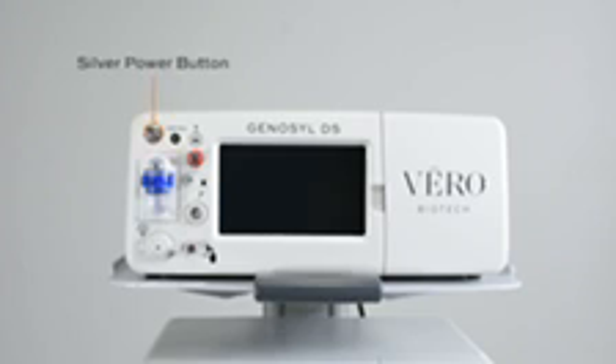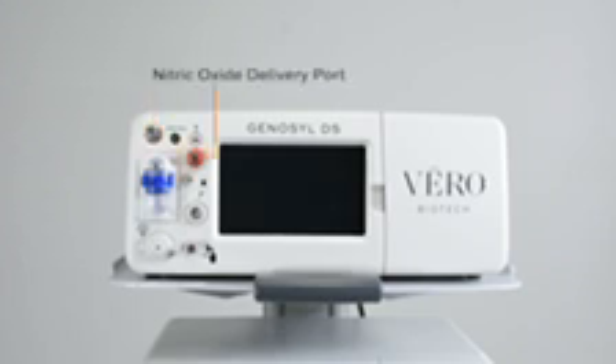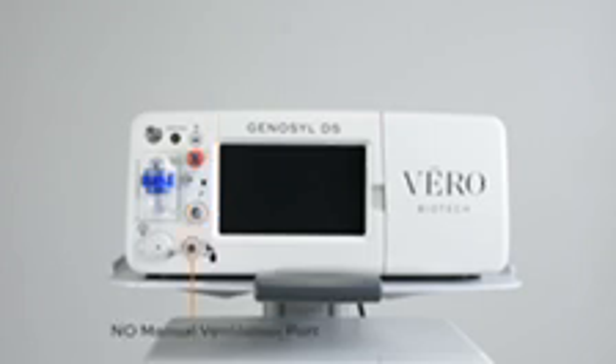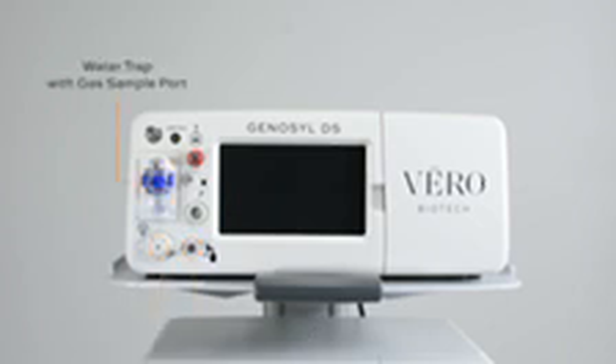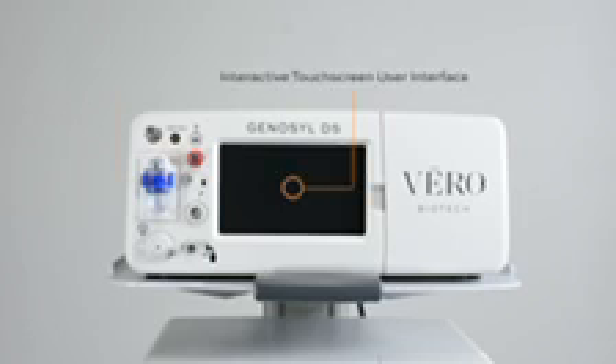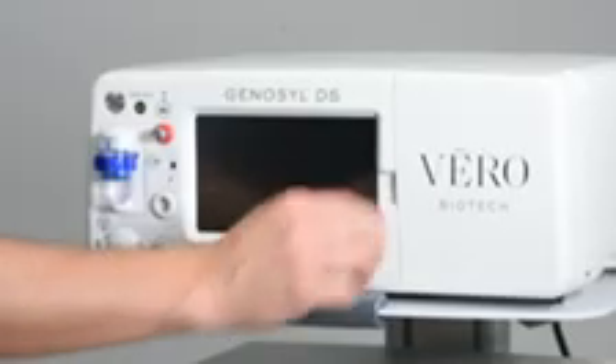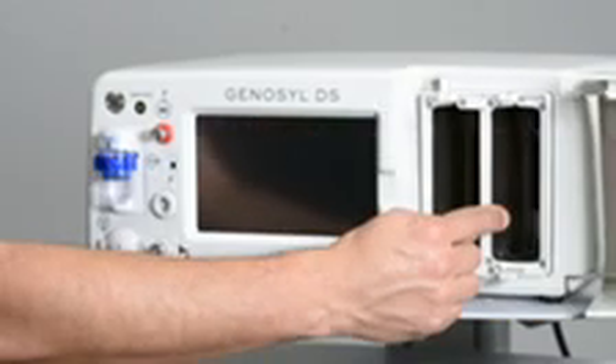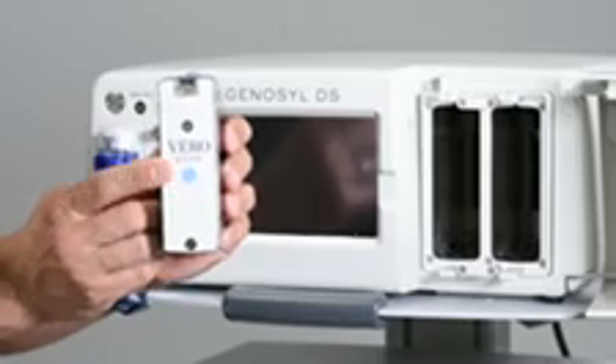Silver on-off power button, nitric oxide delivery port, adaptive sensor port, nitric oxide manual ventilation port, calibration port, water trap with gas sample port, interactive touchscreen user interface, cassette access door, cassette bay, cassette state window. On the back side of the console, you will find the black rocker power switch and the circular power connector.